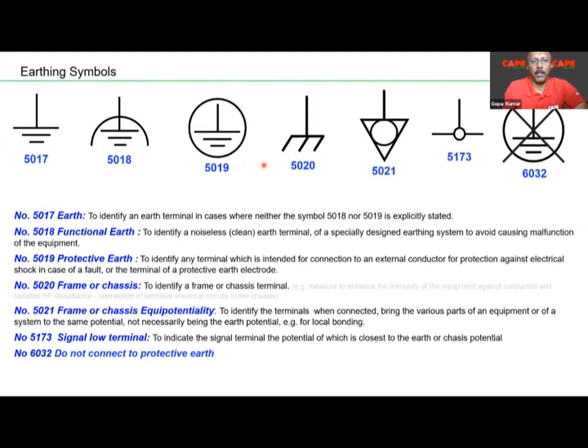5019 is a safety earthing. 5020 is called chassis earthing. 5021 is called frame or chassis equipotentiality. 5173 is called a signal low terminal. Wherever a terminal is marked 5173, you must understand that the potential of that terminal is very close to earth, and it is going to become the reference for the earthing. And 6032 means do not connect to a protective earth. So basically, earthing is done based on its requirement. First, you should understand these kinds of requirements.